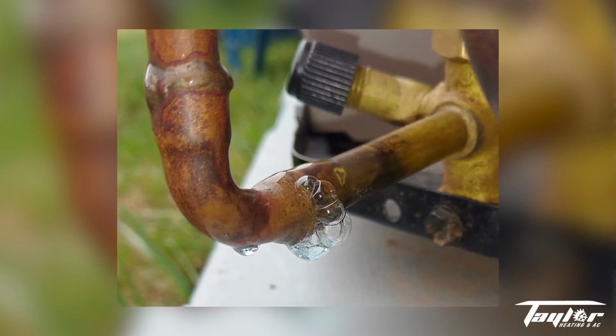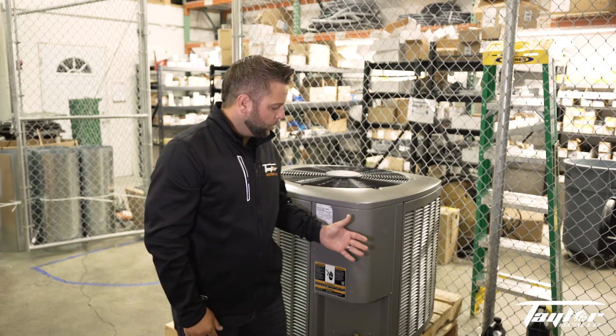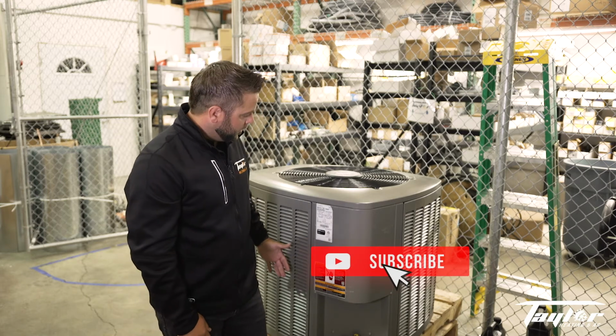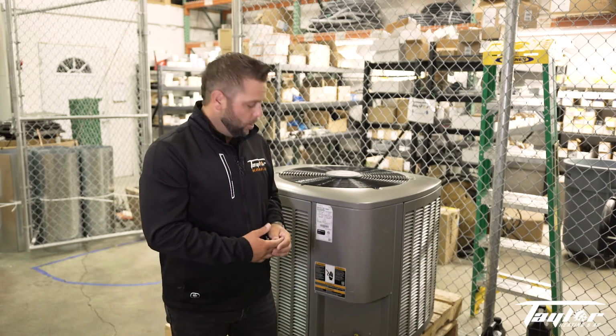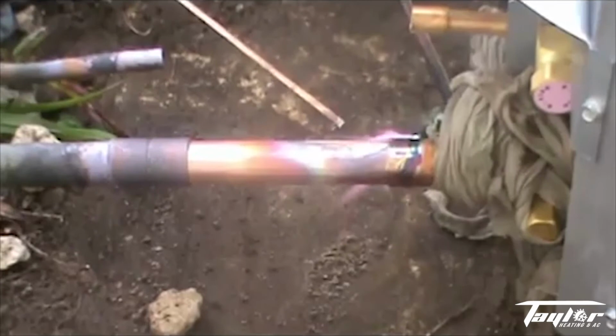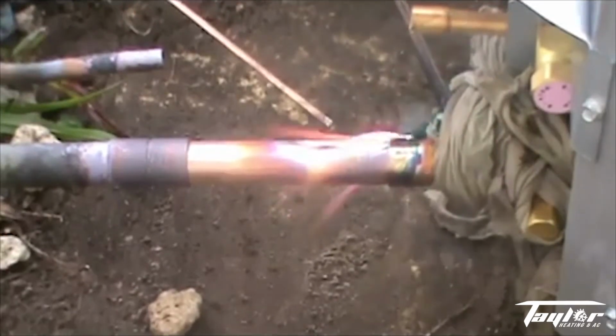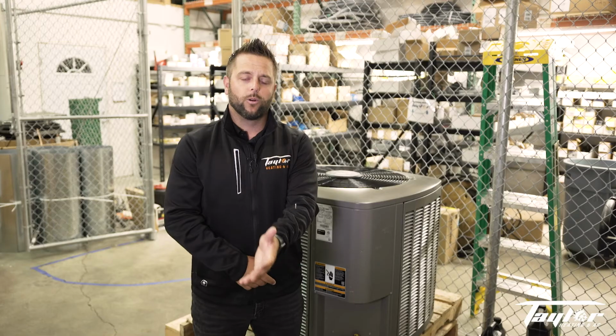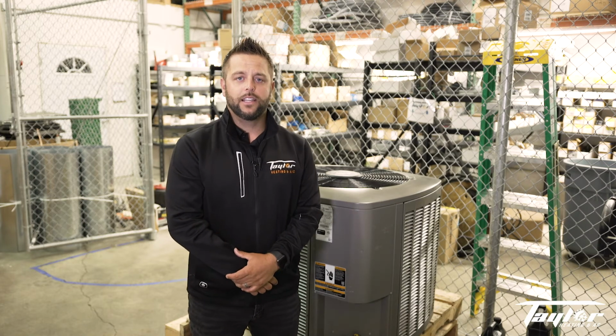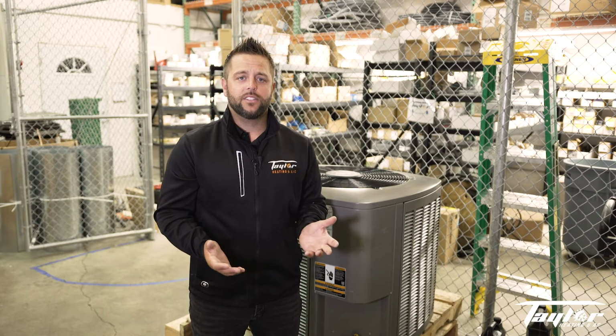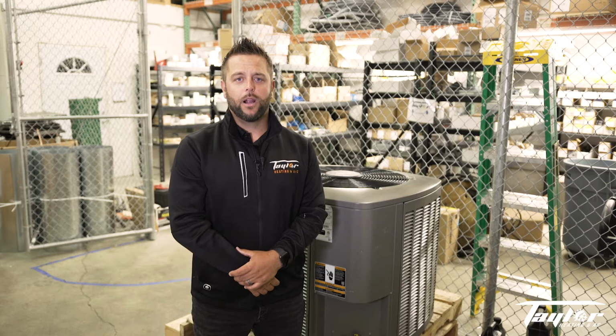If you have a leak within your air conditioning system, it can cause many components inside the system to burn out and can be a very expensive repair. One of the things we always want to do during our maintenance program is check and look for leaks within the system. The outdoor coil can produce leaks that you can see oils falling out of, or down here where we weld at the initial startup of the system, the refrigerant lines coming from the indoor coil to the outdoor unit, we see leaks there as well. There could also be leaks in different fittings and different caps throughout the system.